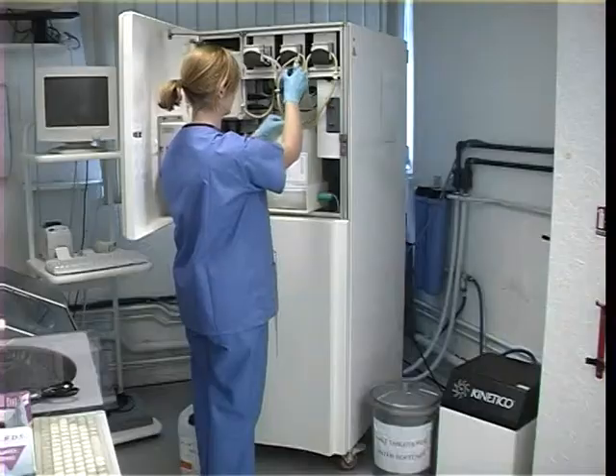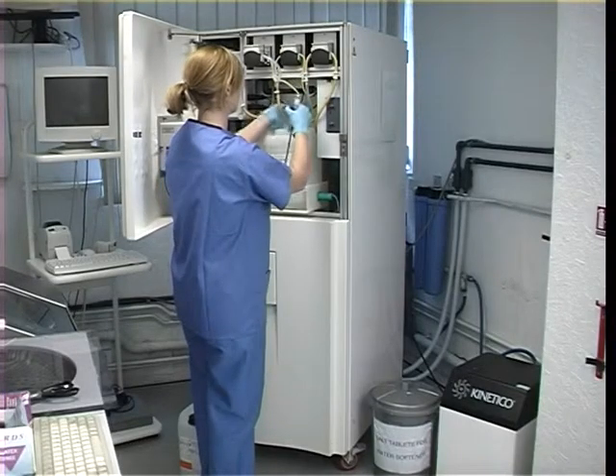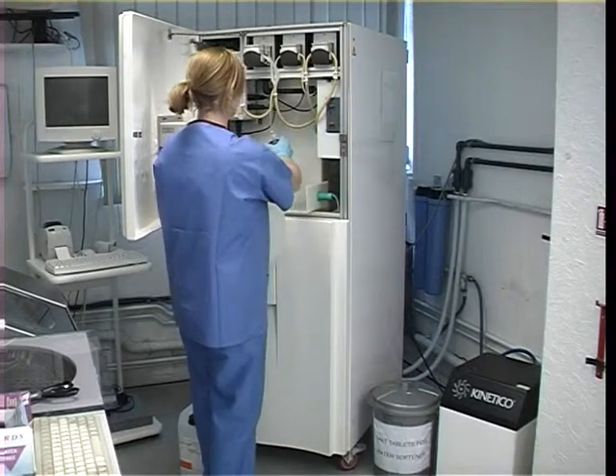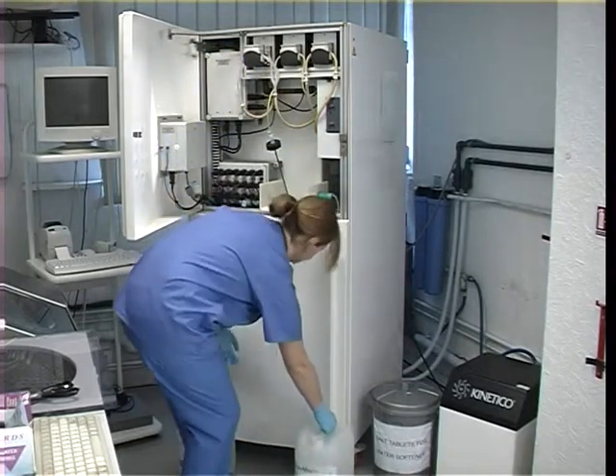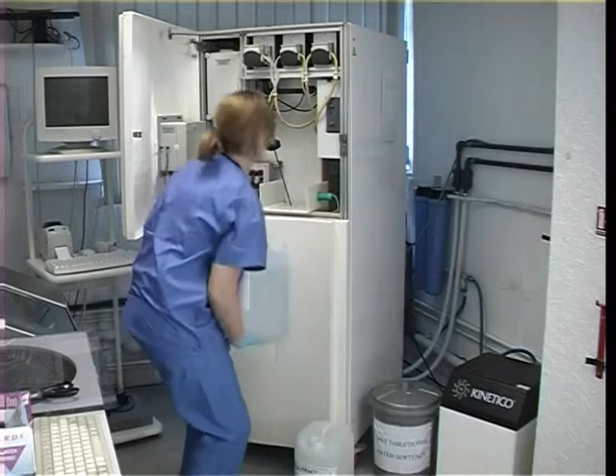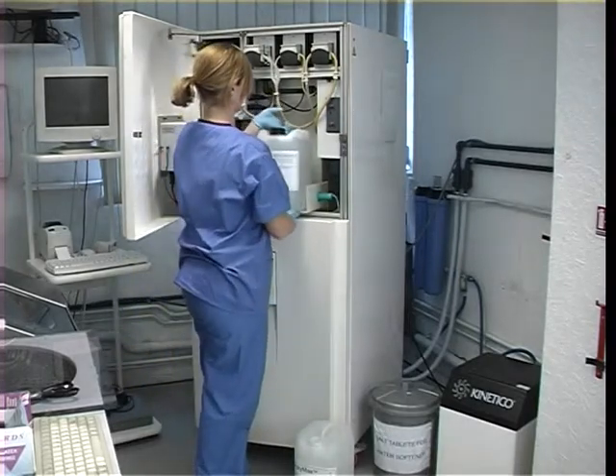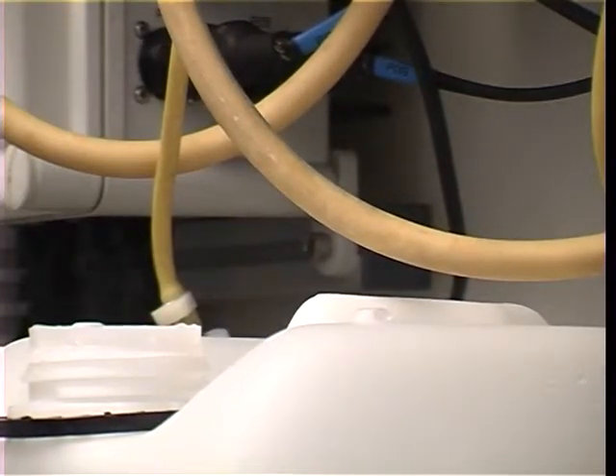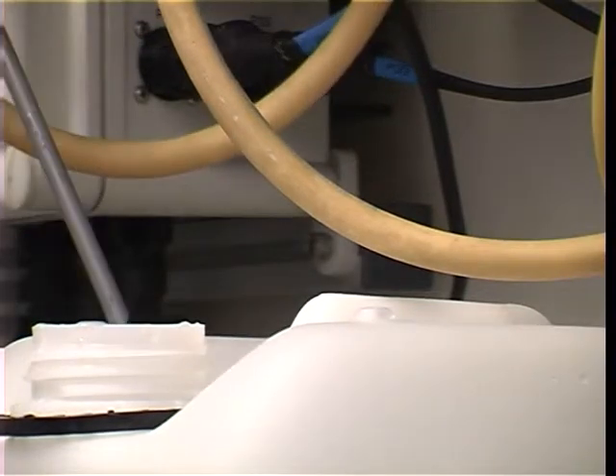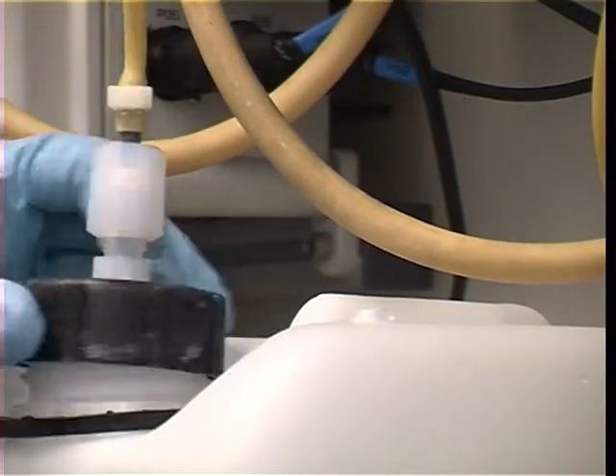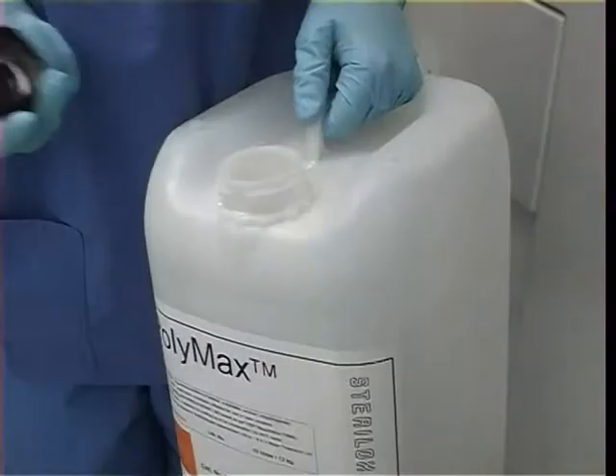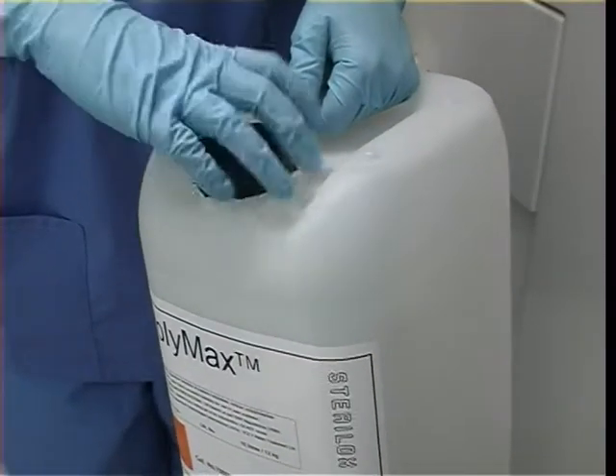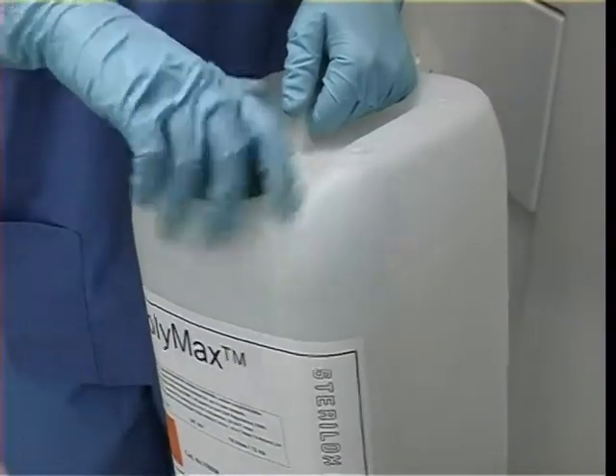Replacement of the Polymax is a simple cap removal and replacement. The generator will give you an audible alarm and a message on the display panel when the Polymax needs changing. You must always practice good handling and lifting techniques when carrying out the task of replacing the bottle. When you have replaced it with a fresh container, use the cap from the new container to seal the finished container for disposal. Dispose of the empty Polymax bottle according to your hospital policy. This is usually in contaminated waste.